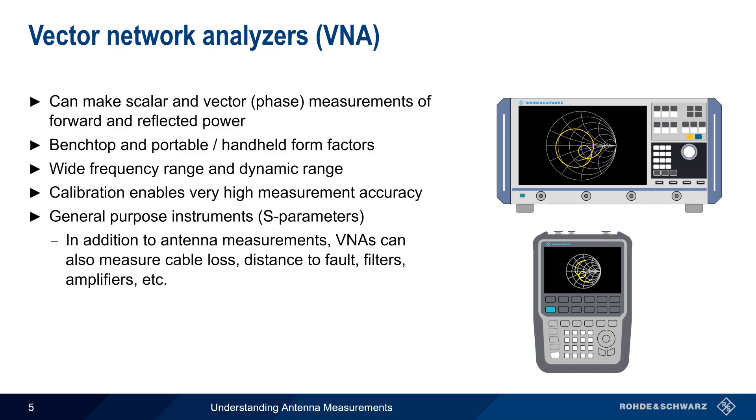It's also worth noting that single-port VNA functionality is sometimes also implemented in spectrum analyzers, by equipping them with a tracking generator and an SWR bridge for separating forward and reflected power.